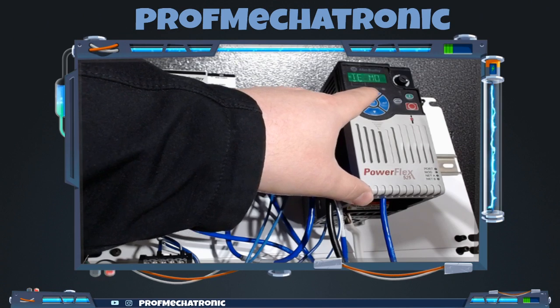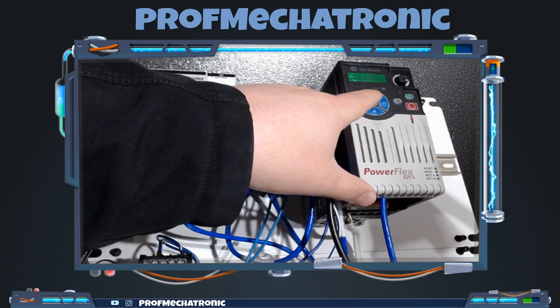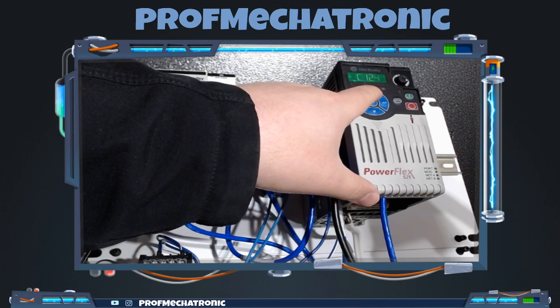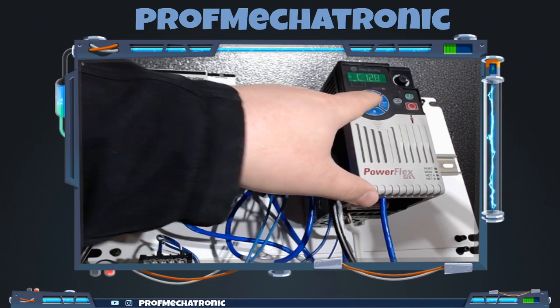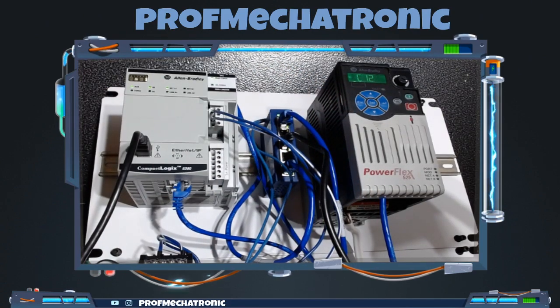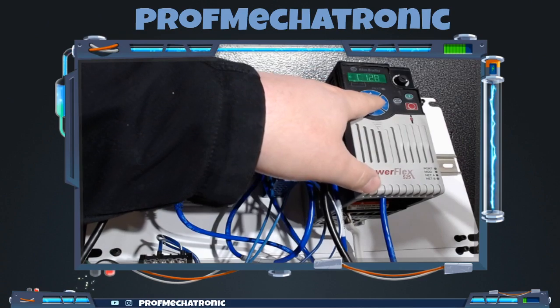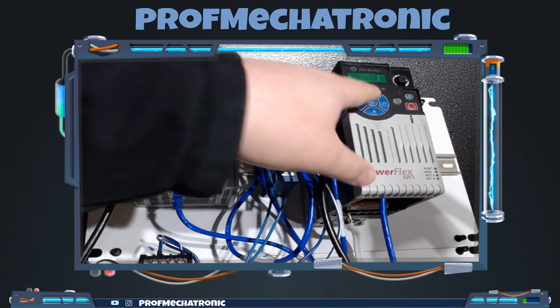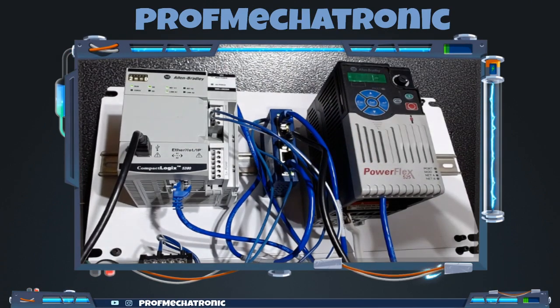So the one we need to look at first, as far as setting up our communications, is address C128. If we look in our manual and look up what C128 is, it's our address selector. So is our address going to be selected from BootP, or is it going to be selected from the parameters?